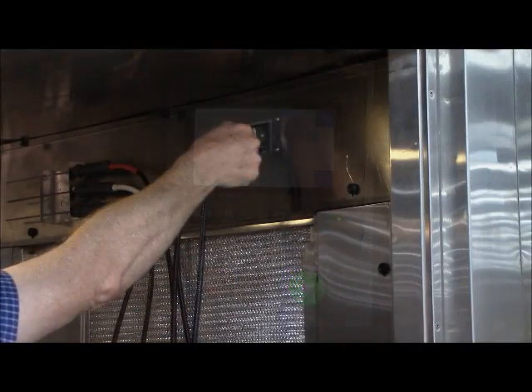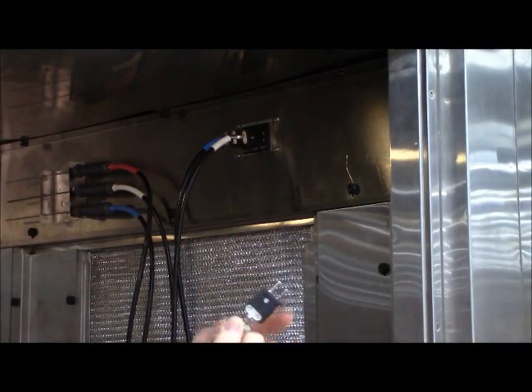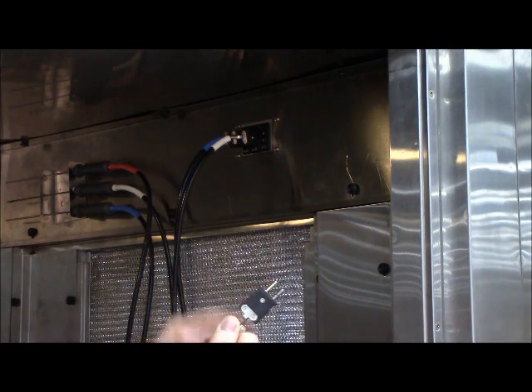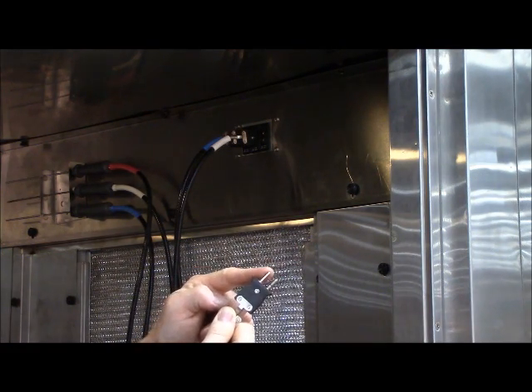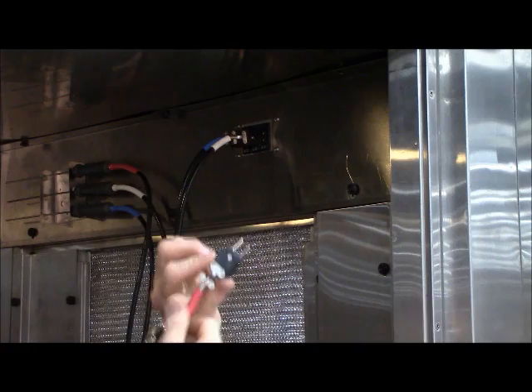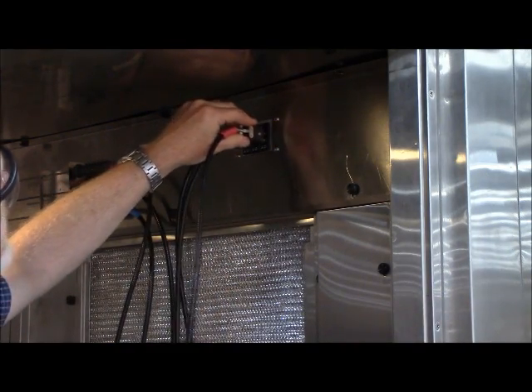Note that there is a large and small prong on the plug. The small prong goes to the top hole of the receptacle. Never immerse the full probe assemblies in the water, just the probe tip and maybe the front end of the handle.